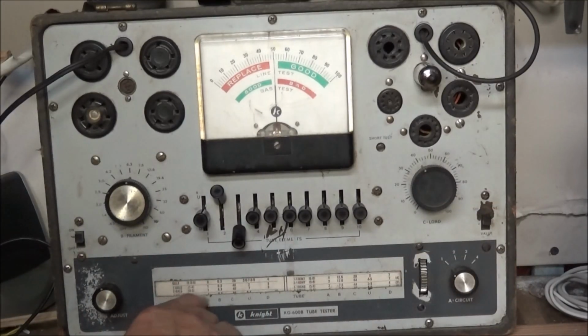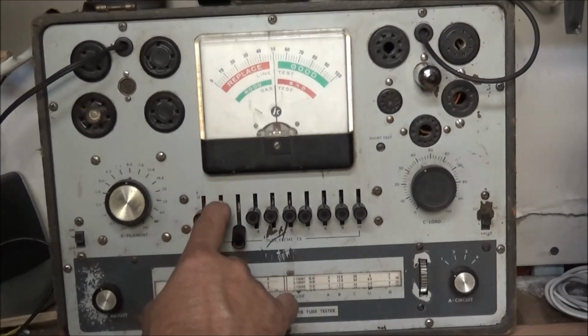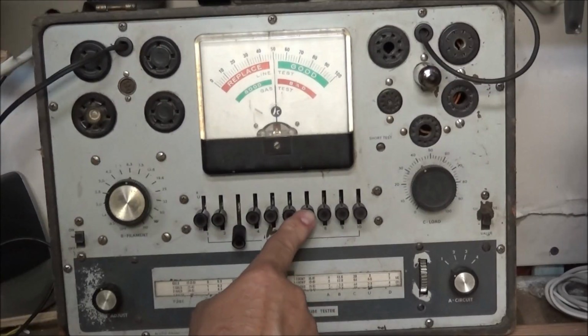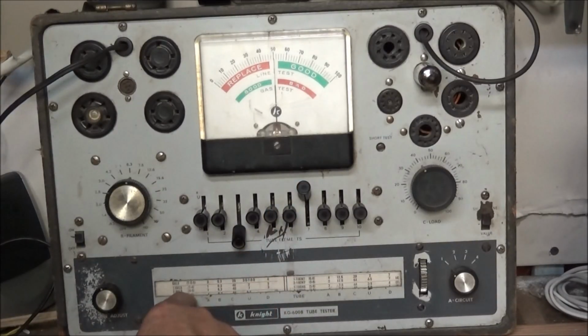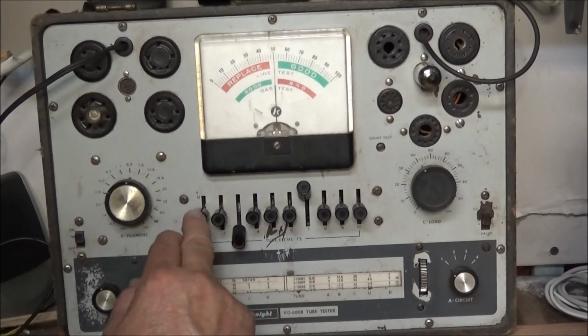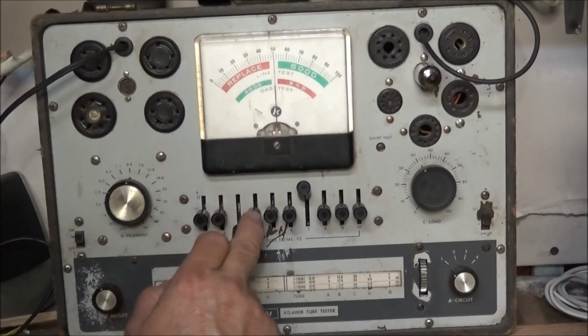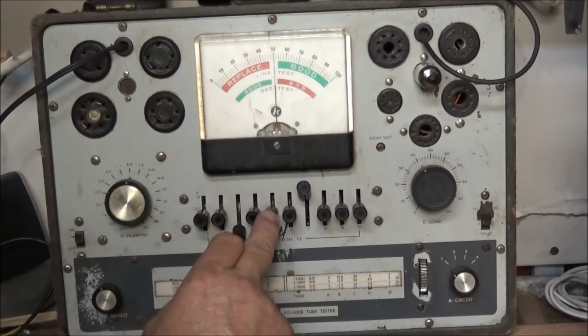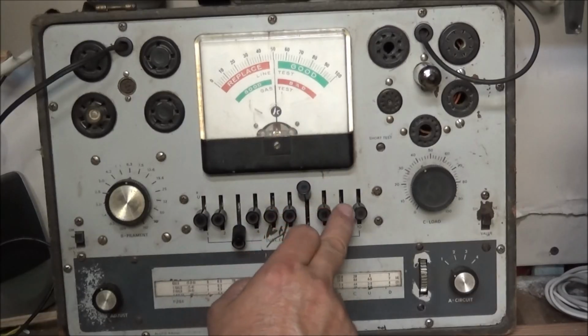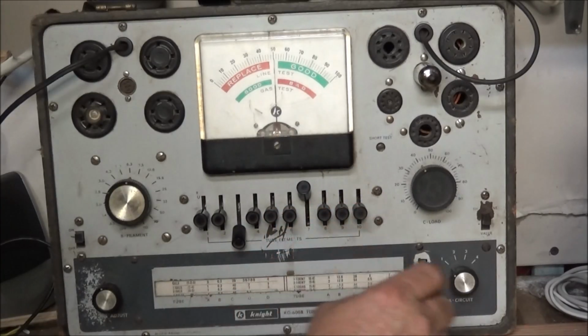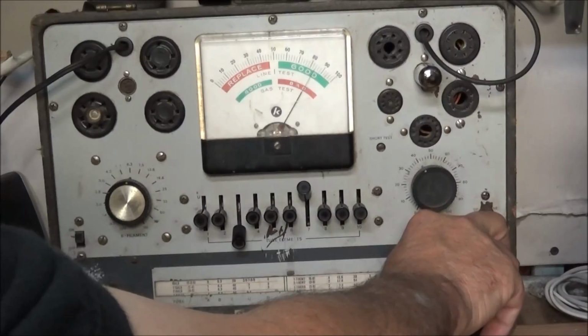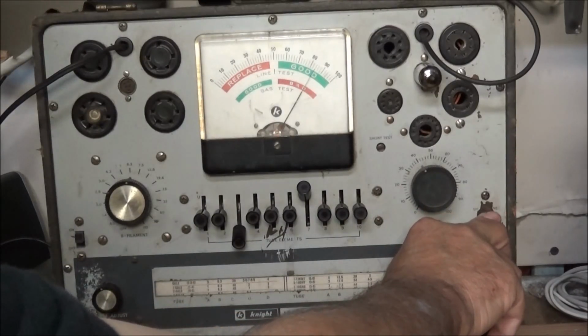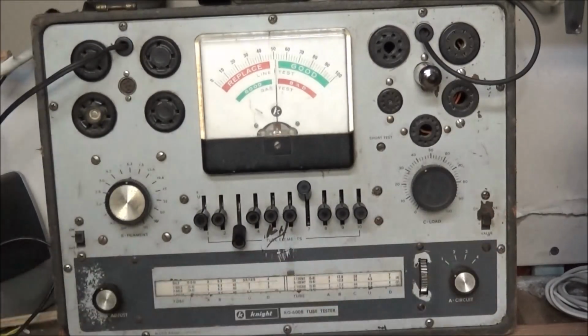So now we want to drop 2 and pick up 7. She's short on 4 and 5 only. Short test looks good. And about 82.5%. So that one there looks good too. So our tube's in great shape.